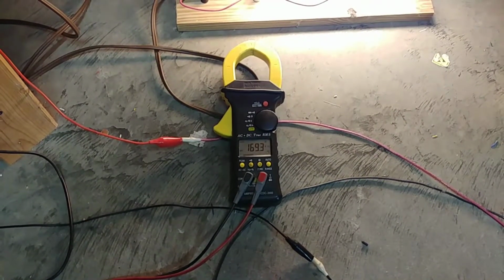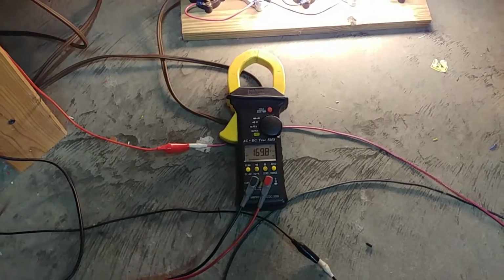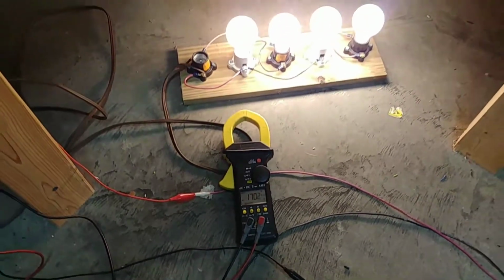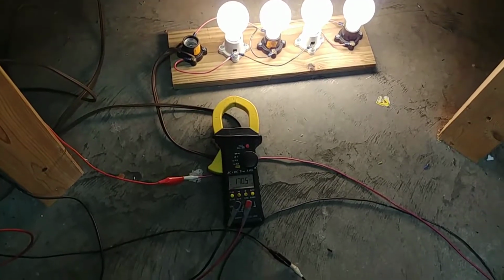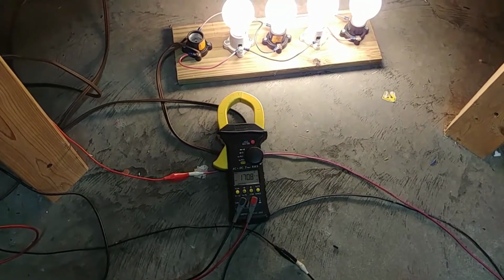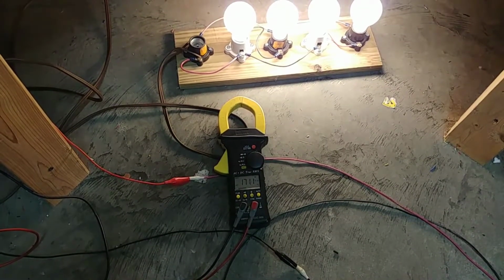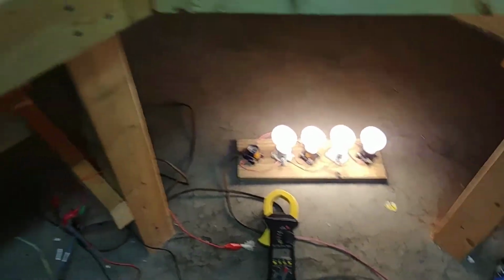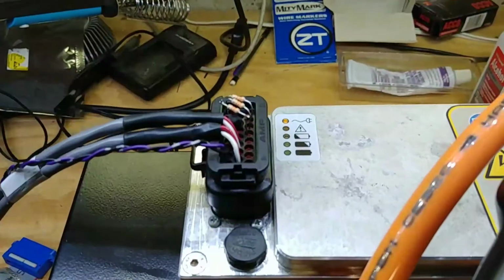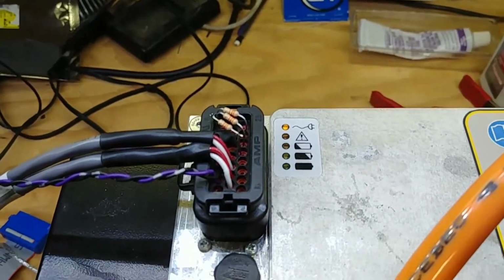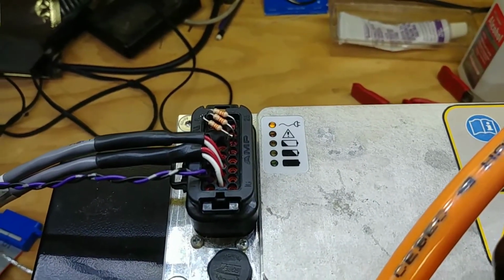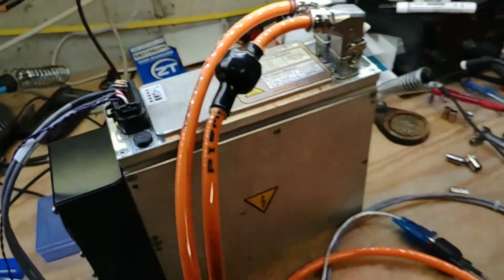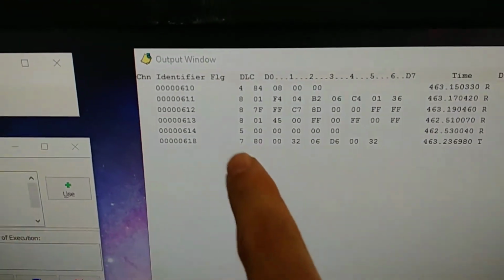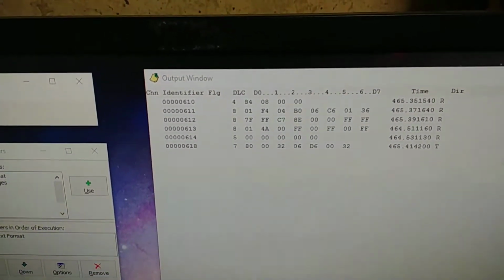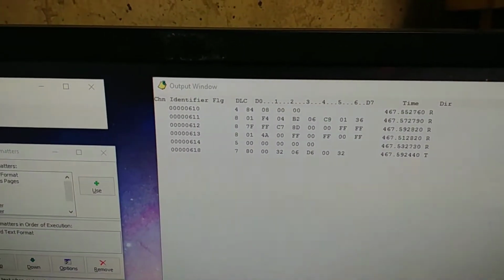Targeting 175 volts, limited to 5 amps, so we're trying to run all these lights and charge the battery simultaneously, and eventually it'll hit 175 volts. If we come over and look, we've got no error message, and we're charging. Everything's working - zeros across the board, no error messages, everything's happy.